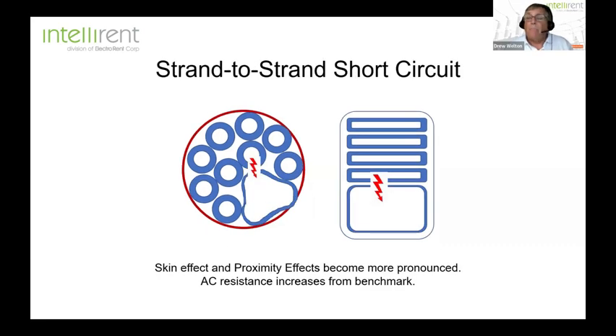Well, what happens, either from manufacturing defect or some failure over time, if these little strands start to short up against each other? That's what we refer to as a shorted conductor bundle. Now, here's the thing about that. This could be part of a manufacturing defect that probably was never checked at the factory, and they probably never ran this test when they commissioned the transformer. It's definitely not going to show up on any normal electrical test that you do on a transformer. This is the only test that will indicate this problem.